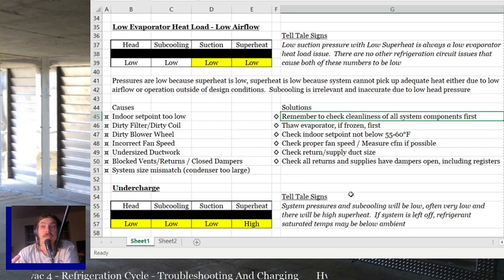Check your return and supply duct size. We'll learn later this year how to properly check the size of the supply and return ducts, but you need to check and make sure the size is proper. You need to make sure the filters are sized properly. It's another thing, the filter's really dirty, so you get low airflow. Well, really dirty filters are usually because of undersized filters. So it could be that the filter's been undersized the whole dang time, and that's a big part of the problem. Check all your returns and supplies have dampers open, including the registers. They can't block return ducts.